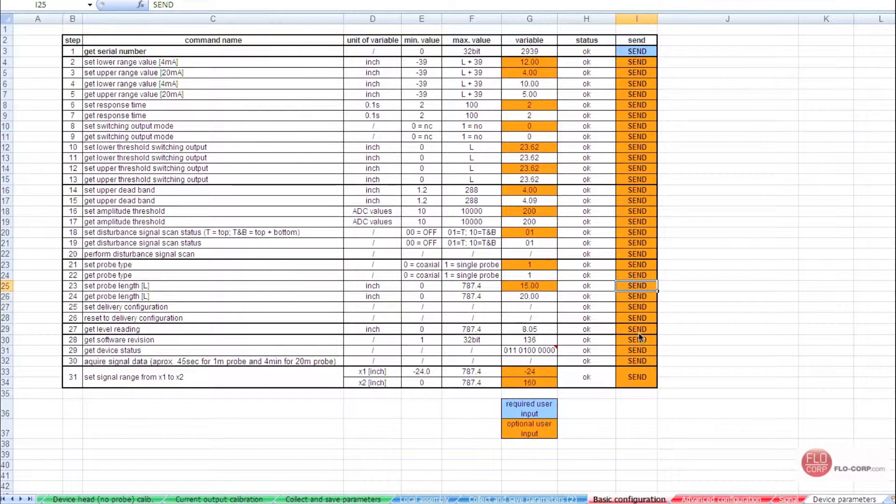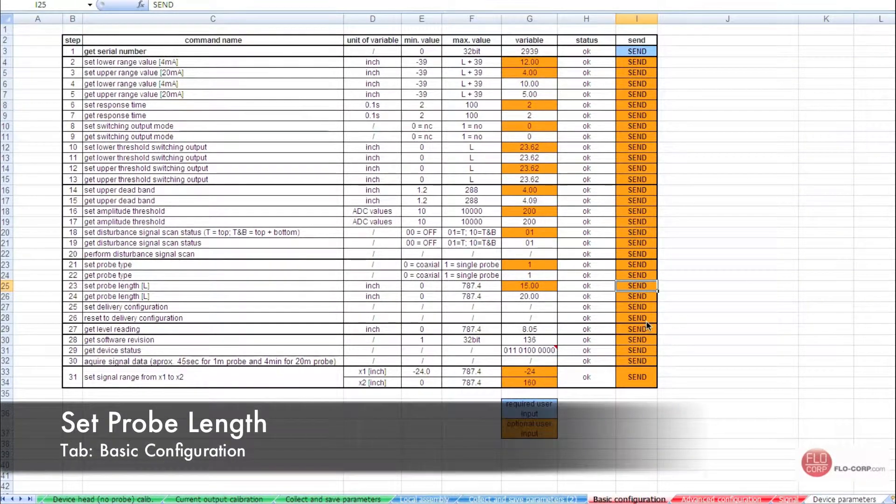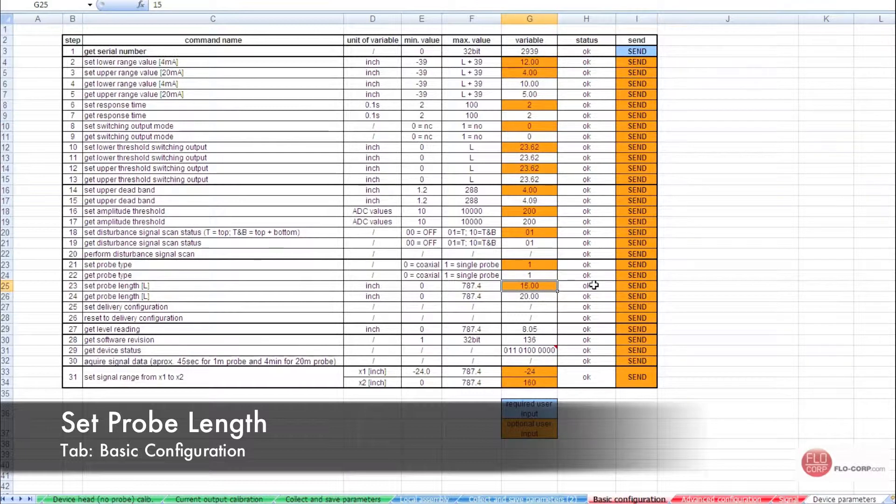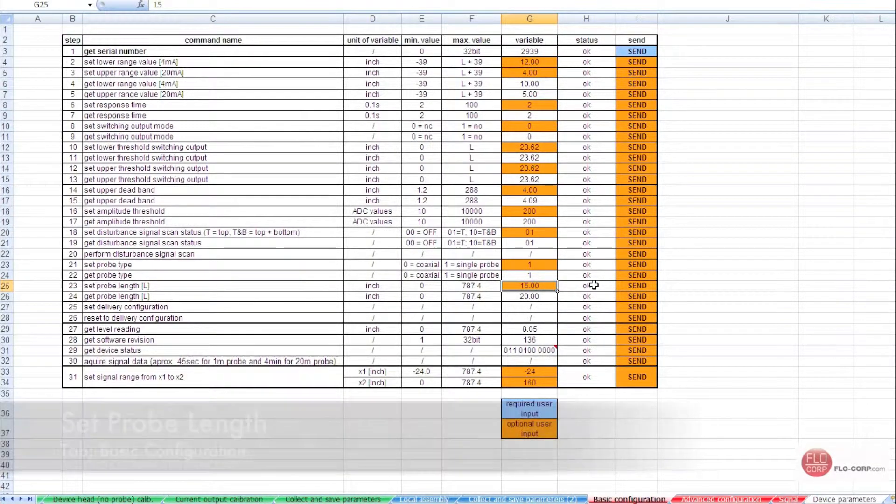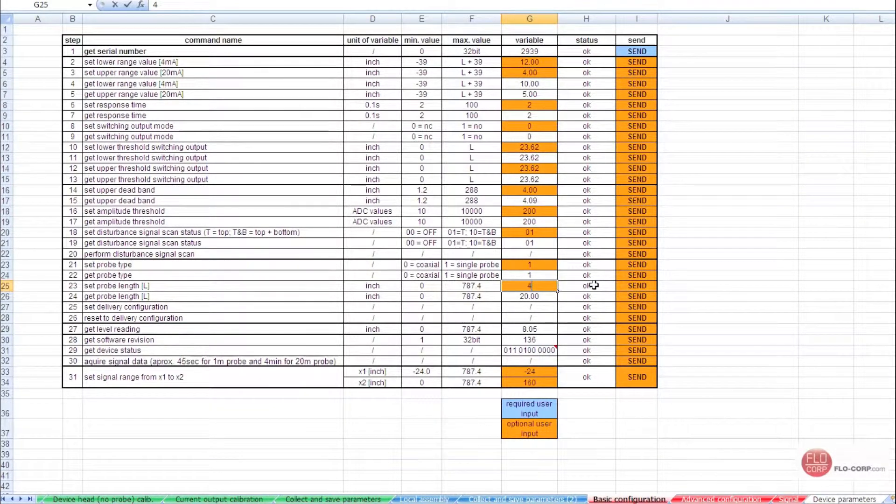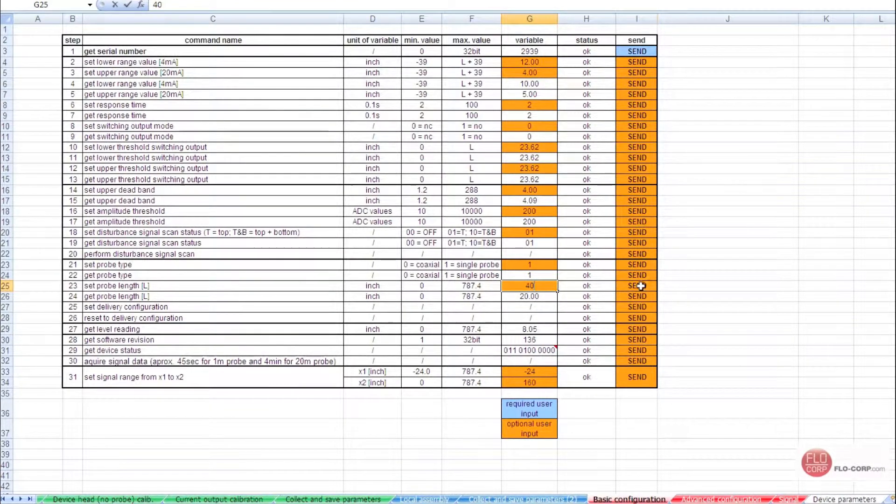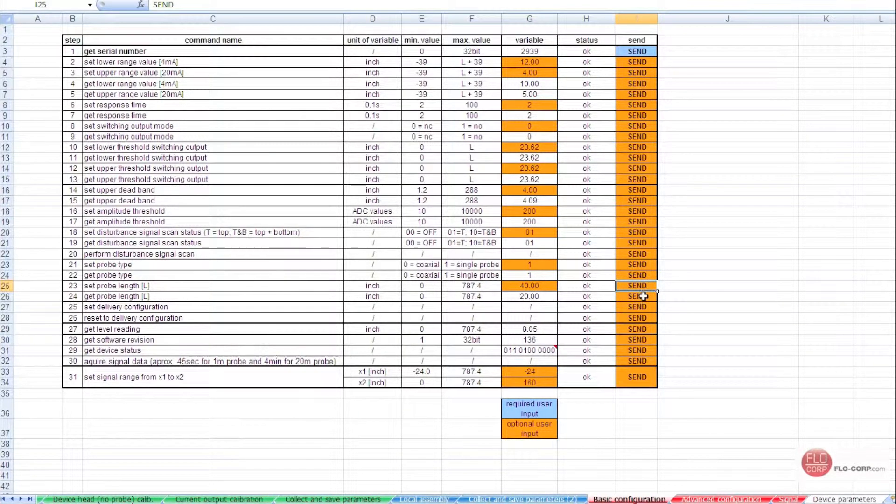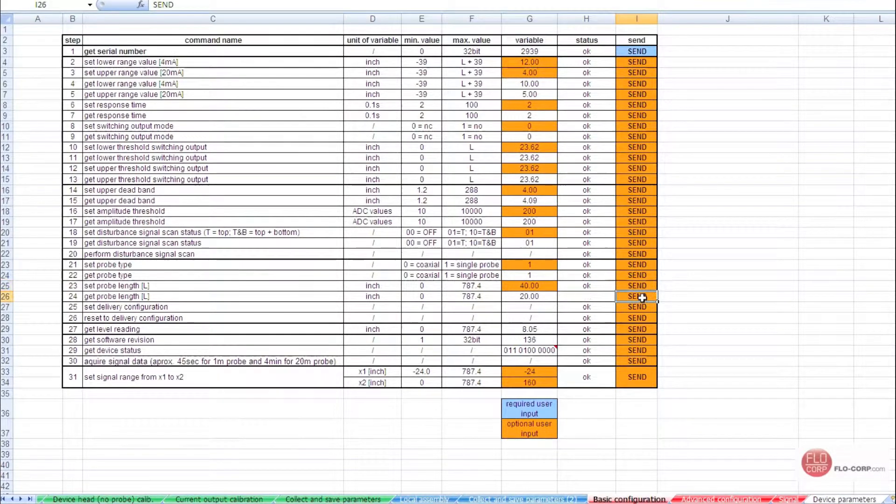Another setting that can be adjusted is setting up the probe length. For instance, we can select this box, type in a probe length, we'll use 40 for 40 inches, and send the command. We can confirm that 40 inches is the probe length by selecting this command, get probe length.